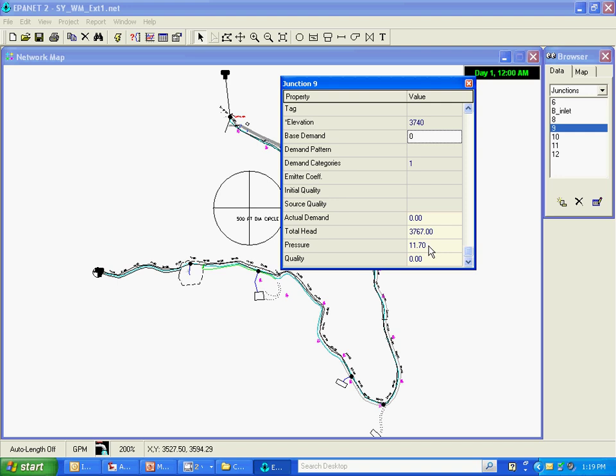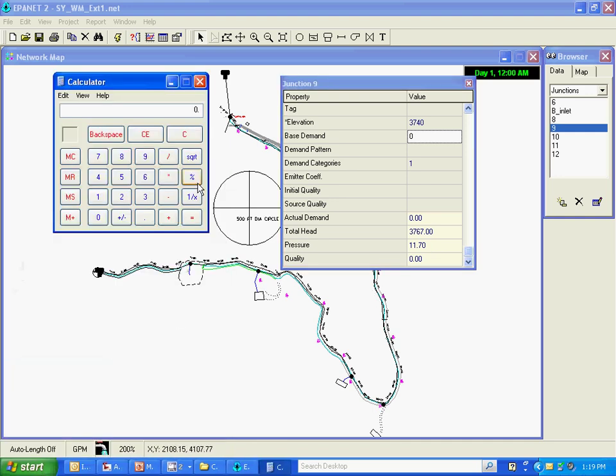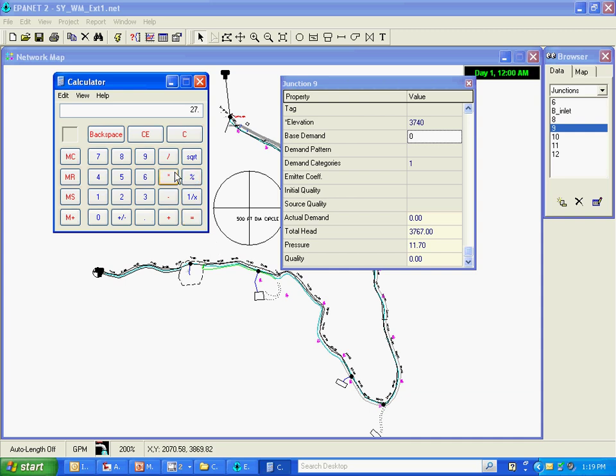Let's see if we get a similar pressure by doing a hand calculation. I'm just going to grab my calculator here, so 3767 subtract 3740. That's 27 feet. Let's convert that over to psi by dividing by 2.3. And we get a fairly similar answer with 11.74 and the model's calculating 11.7, so I'm pretty happy with that accuracy there.